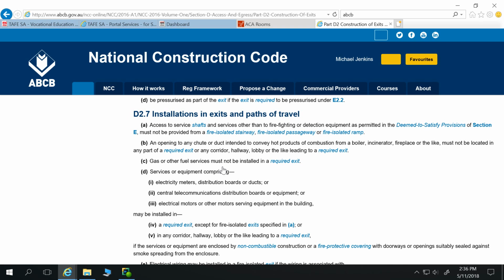Any opening to a chute or duct intended to convey hot products of combustion from a boiler, incinerator, fireplace, or the like must not be located in any part of a required exit, or a corridor, hallway, lobby, or the like leading to a required exit. That's a bit of a no-brainer. You don't want burning stuff inside an exit. Gas or other fuel services must not be installed in a required exit.